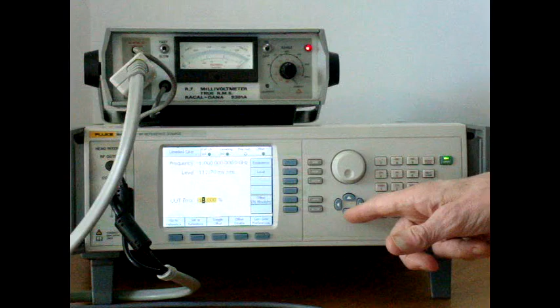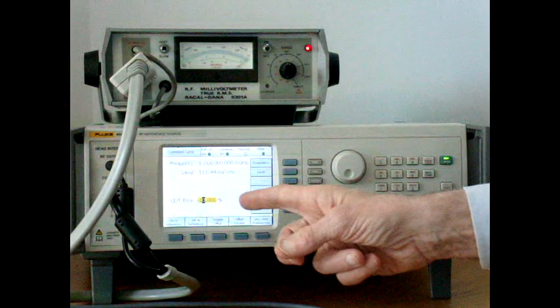And I'm going to make use of the scroll wheel and then the up-down keys to set exactly a full-scale reading. And now we can see exactly the error of the unit under test with no need to make any calculations or take into account any other sources of measurement error, because my 9640 is delivering the signal directly into the UUT input. Now we can go on and make some measurements at some other frequency points, and if I want to do that I might like to go quickly back to my reference point to check that nothing has drifted before I go on to make some measurements at some other different frequencies.